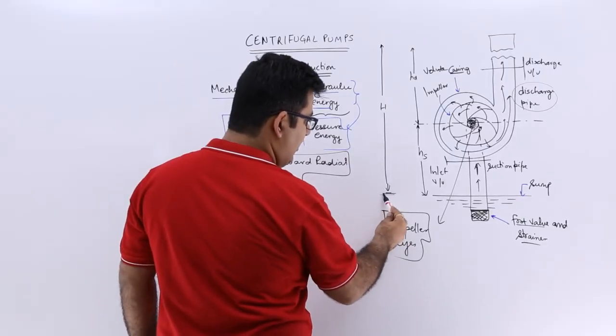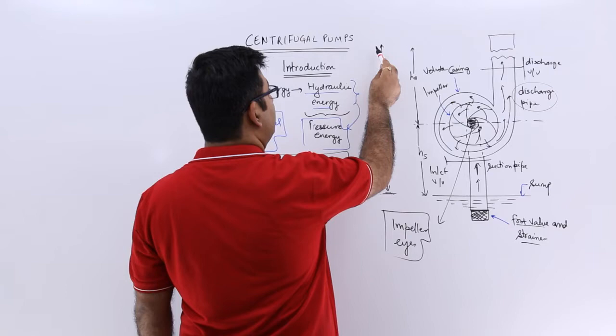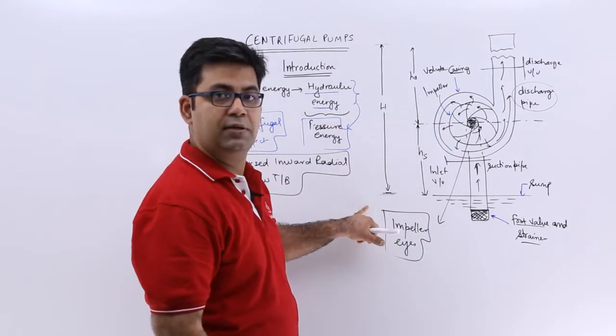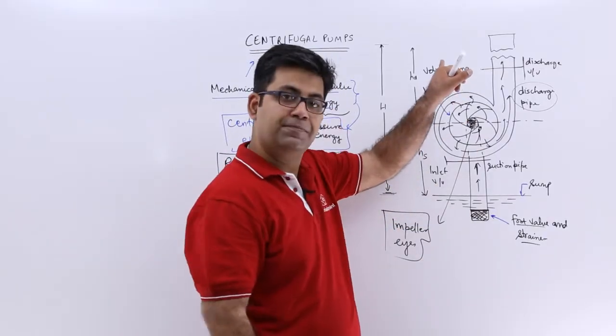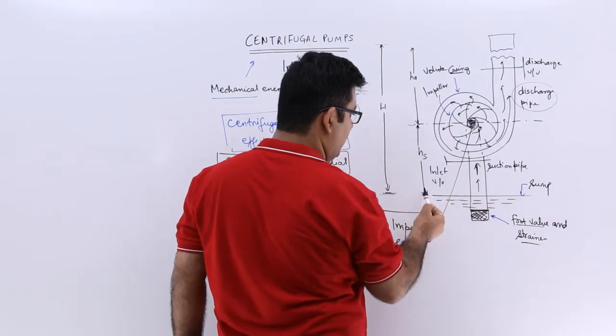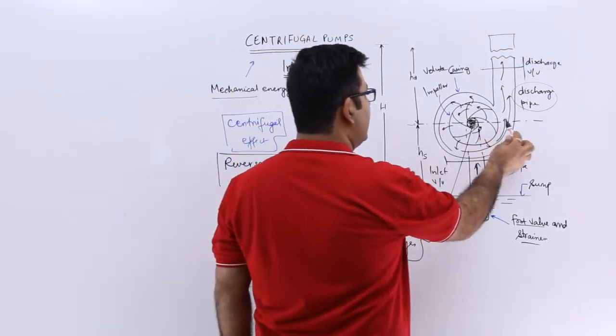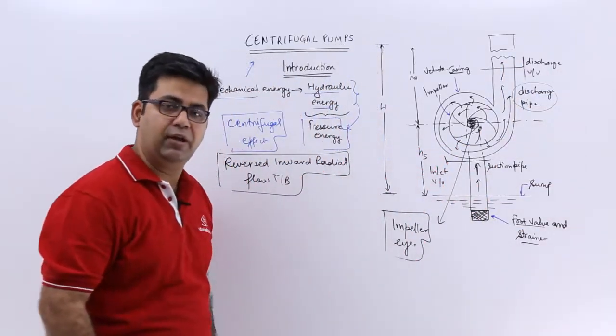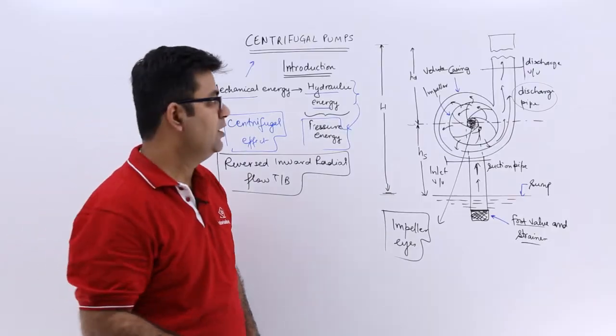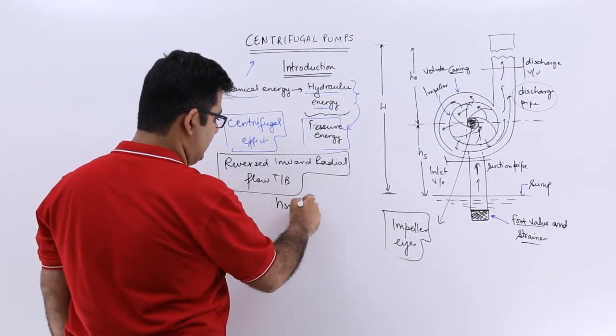Now if you look at this level, from this level to this level, this is the total head by which the liquid has to be raised. Till the center of the eye, this is the suction head and from the center of the eye to the point of the delivery, the highest point of the delivery, you have the discharge head.